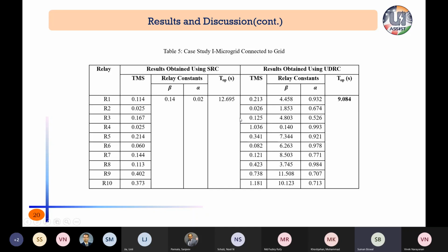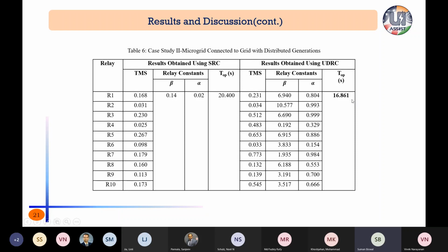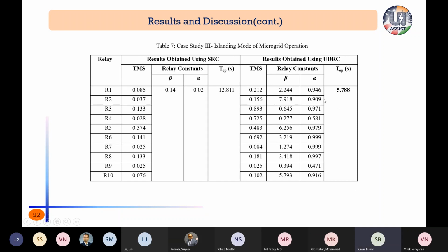Now we consider the UDRC scheme, or non-standard tripping characteristics, where we varied beta and alpha. We found that when we control more parameters of the relay, better solutions are obtained, and also better coordination criteria. Here the operating time is also improved for all the 10 relays, because we have 5 lines and each line has 2 relays. So better performance is noticed for the UDRC scheme. Similarly, the second case study also gives better results. Third is the islanding mode, where beta and alpha are also taken as variables, and it gives better results.